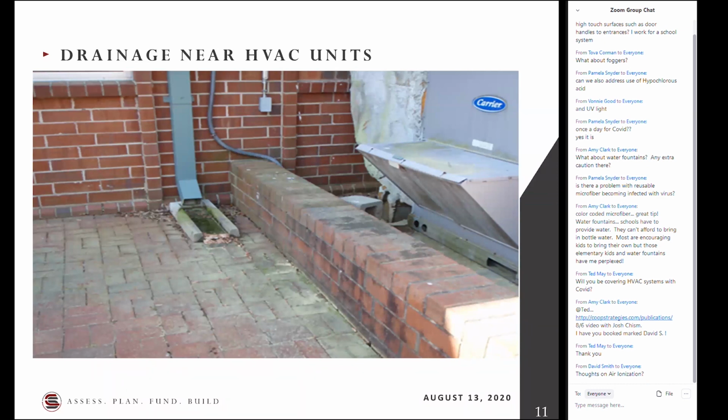This picture, the woman whose classroom was served by that unit was complaining about allergies. We went outside, we looked at the outdoor air intake, and we saw this downspout right next to the outdoor air intake, and it's green with algae, and the brick's green with algae. No wonder she's complaining, right? So you want to bring clean air into the building if you can. Yeah, I think that's crucially important.